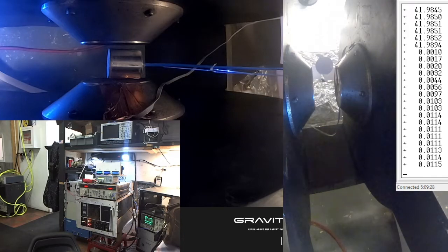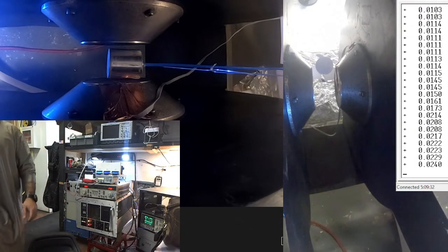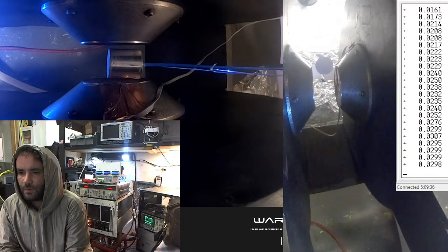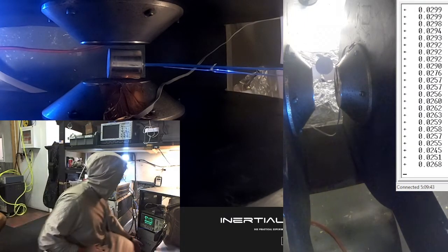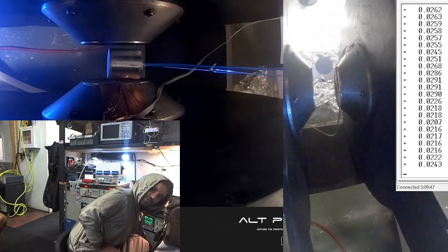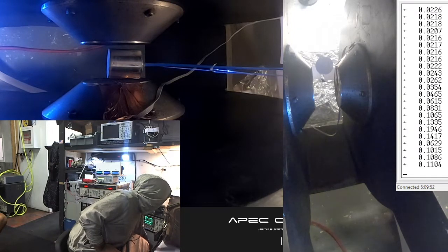We've got to really zoom into that sample and watch it closely, because if it moves when the magnet gets turned on, and it shouldn't, because there should be no magnetic element in there, that thing should stay pretty much exactly where it's at when the magnets and the RF get turned on. They shouldn't shift. The magnet right now. I'm watching it real closely. Turning it on. 3, 2, 1. It's going up. At full power.